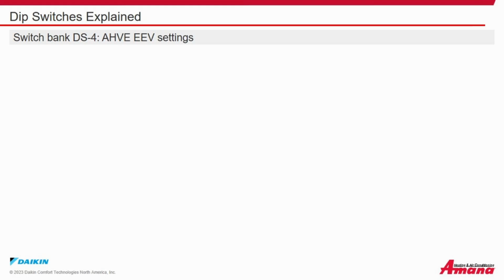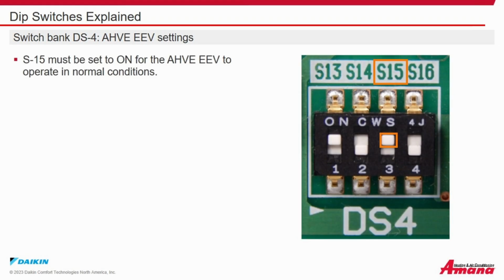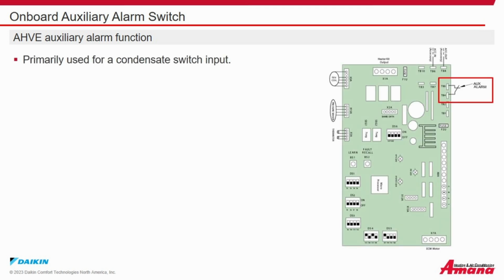Switch bank dip switch 4 on the AHVE for electronic expansion valve settings. S15 must be set to on for the AHVE EEV to operate in normal conditions. S16 is not used. Onboard auxiliary alarm switch. The AHVE auxiliary alarm function is primarily used as a condensate switch input.